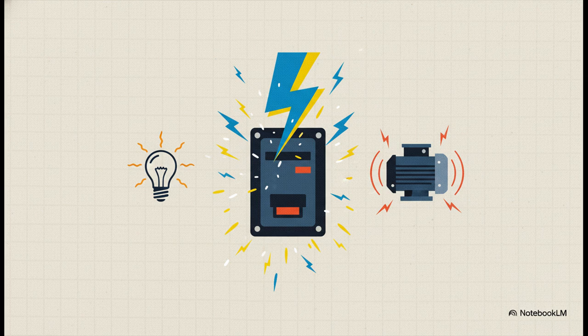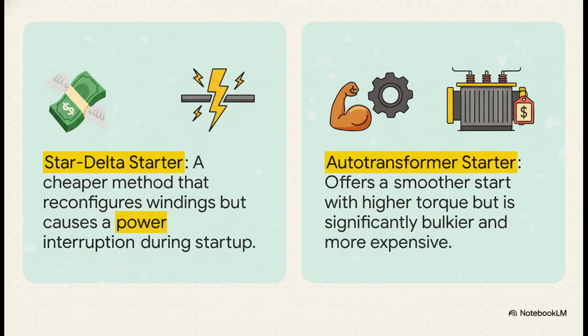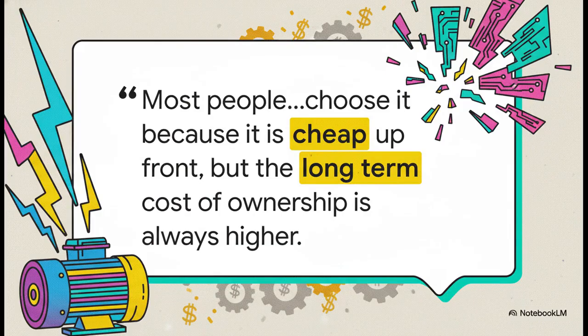So to fix this, engineers came up with reduced voltage starters. For a long time, you basically had two main choices. The star-delta starter was the cheaper option, but when it switched from start mode to run mode, it created a brief power interruption that caused its own set of problems. The other option, the auto-transformer starter, gave you a smoother start with more torque, but it was way bigger and a lot more expensive.